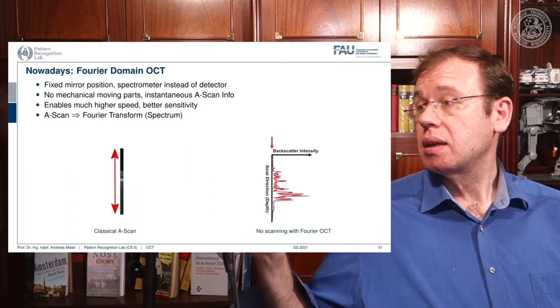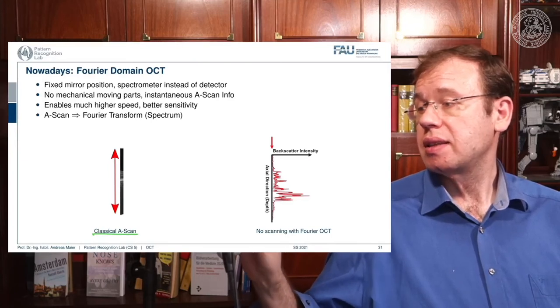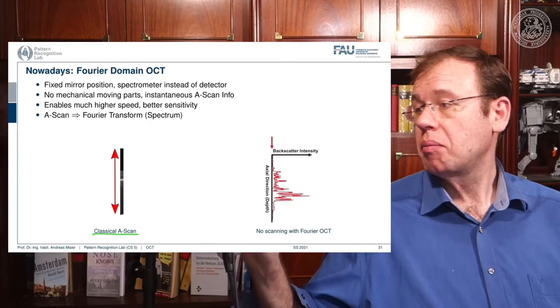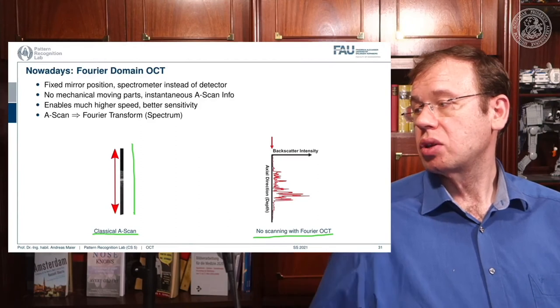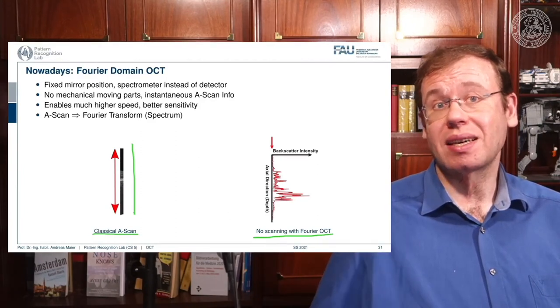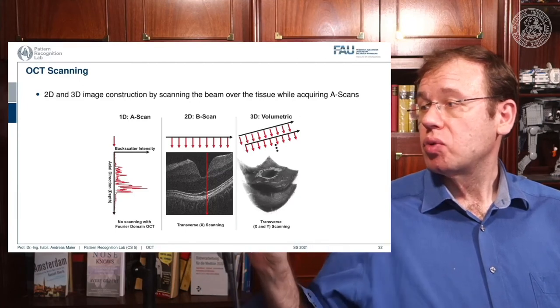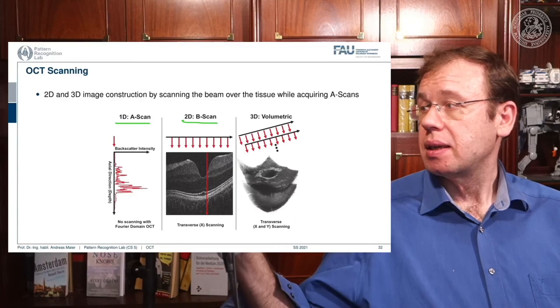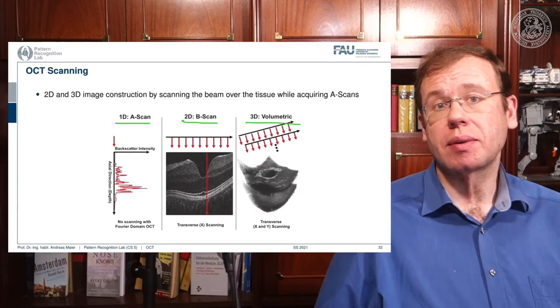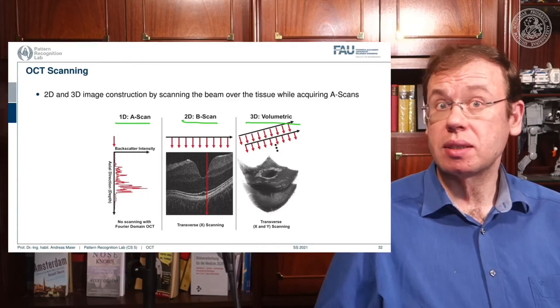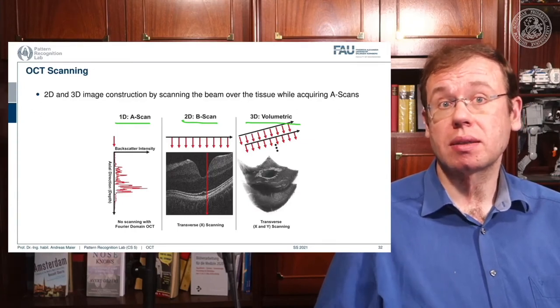Nowadays Fourier domain OCT is the standard. In classical time domain OCT you have to mechanically move the mirror to get the depth profile. With Fourier OCT, no additional scanning is required — you instantaneously get the entire A-scan in a single shot, with higher speed, better sensitivity, and no moving parts. Combining A-scans, B-scans, and volumetric acquisitions allows scanning of entire 3D volumes of the retina.